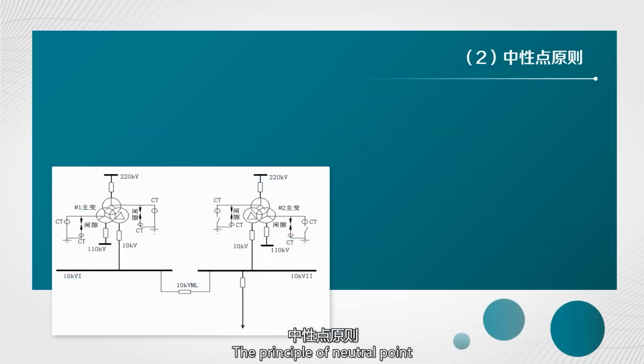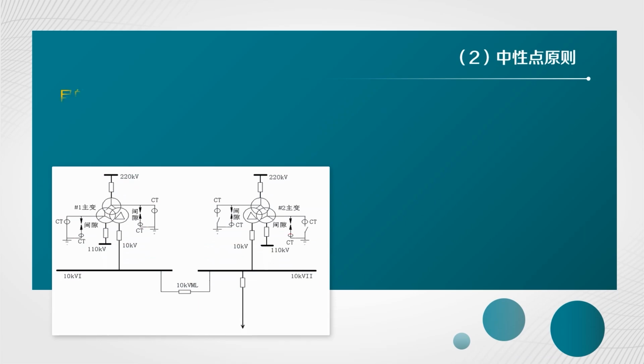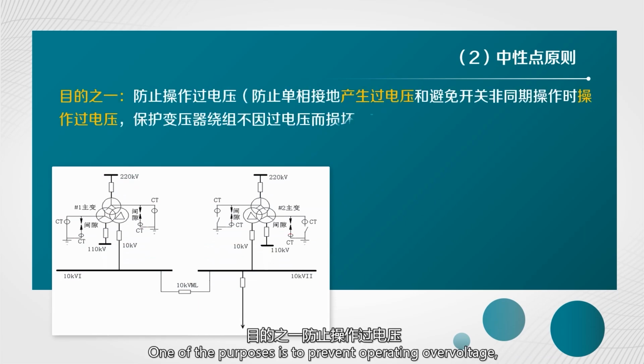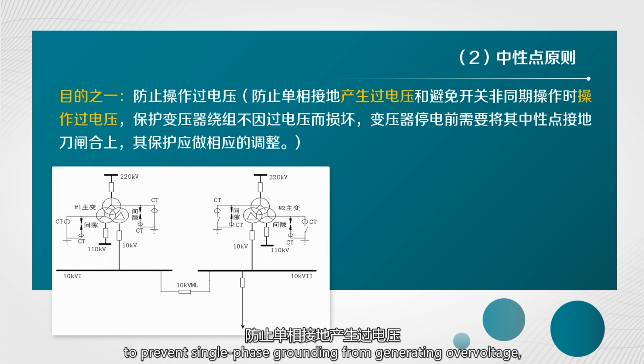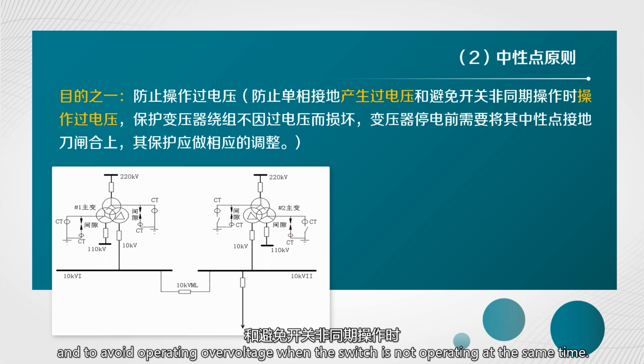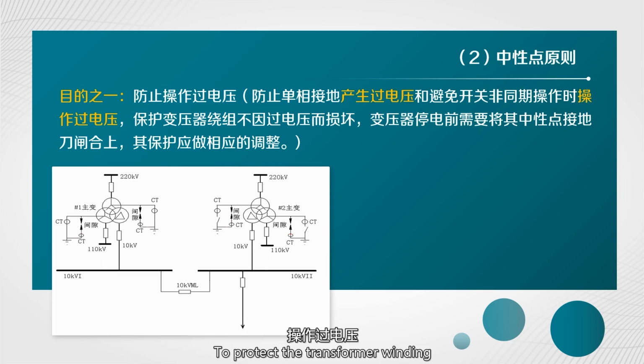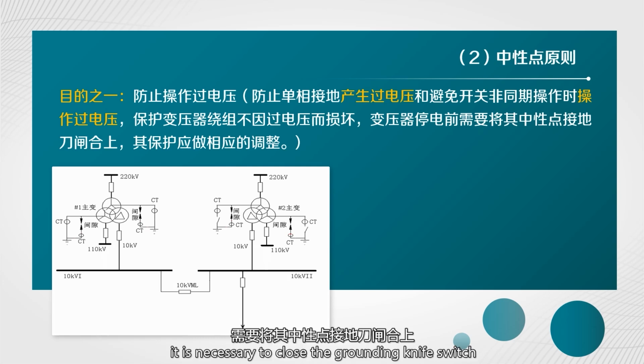The principle of neutral point mainly considers 2 purposes. One of the purposes is to prevent operating overvoltage, to prevent single-phase grounding from generating overvoltage, and to avoid operating overvoltage when the switch is not operating at the same time. To protect the transformer winding from being damaged by overvoltage, before the transformer is powered off, it is necessary to close the grounding knife switch at its neutral point and its protection should be adjusted accordingly.